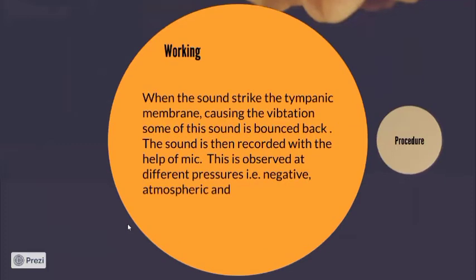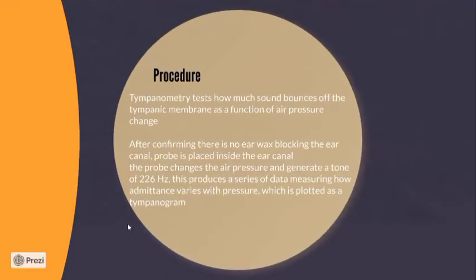Now, how does the tympanometer work? The basic tympanometer working is that when the sound strikes the tympanic membrane, it causes vibration. Some of these vibrations are bounced back and are recorded with the help of the mic. It is observed at different pressures, like negative, atmospheric, and positive pressures. The test is performed when the tympanometer tests how much sound bounces off the tympanic membrane as a function of pressure change.